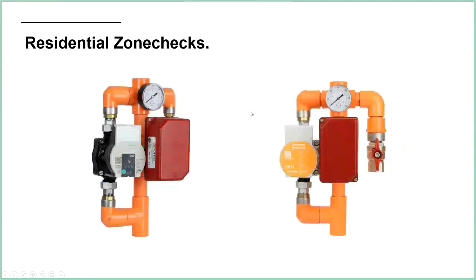Thank you. Okay, so here are a couple of products which we sell. Project Fire products. These are residential zone checks. Here we have the flow switch incorporated. We have our pressure gauge, and we have our bypass line with pump. This is a way of testing the flow switch using this kind of circulating system rather than discharging water.